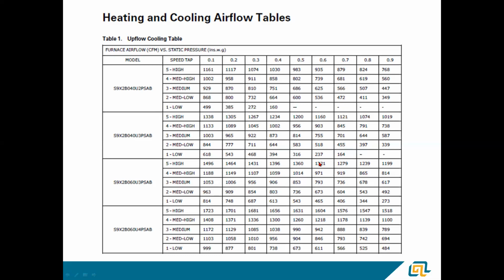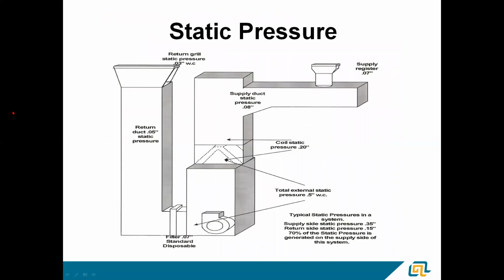But if you look down the chart, as our static pressure increases, that airflow drops off dramatically. At 0.9, you're still making it, but that blower is working hard. We're drawing some pretty high amperage, and of course, it's not the most efficient thing for the consumer. So got to keep an eye on that static pressure. Keep it down around that 0.7. 0.5 is the rated, but if you can do 0.7, you're pretty good.